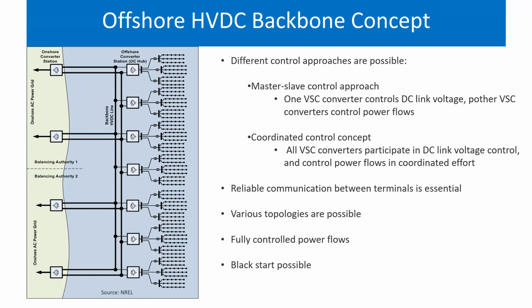Another important factor that people don't talk about much is the resiliency of this approach: the voltage source converters used in multi-terminal HVDC systems can also have black start capability. So any portion of the onshore grid can be black started either from offshore wind or from a neighboring region using this technology. It's a very promising approach, and it doesn't need to be developed right away along the whole coast of the United States. It can be done in a phased and planned approach, step by step, but with this capability in mind.